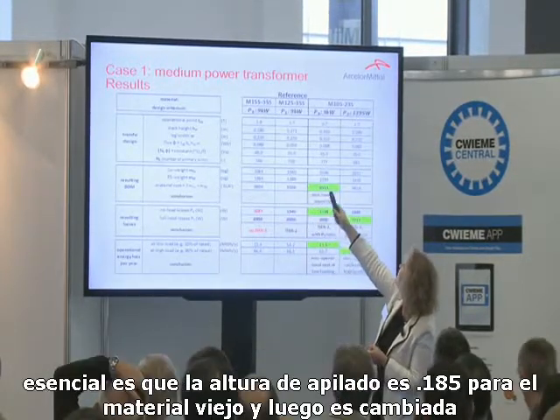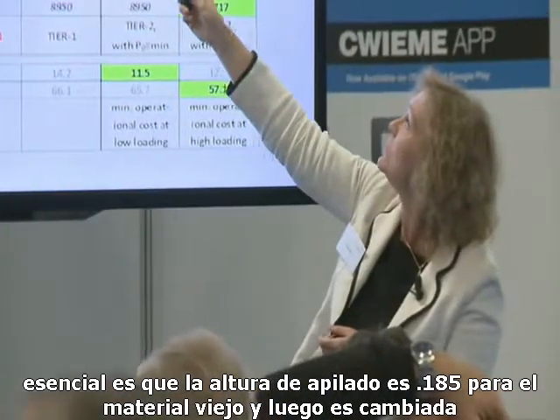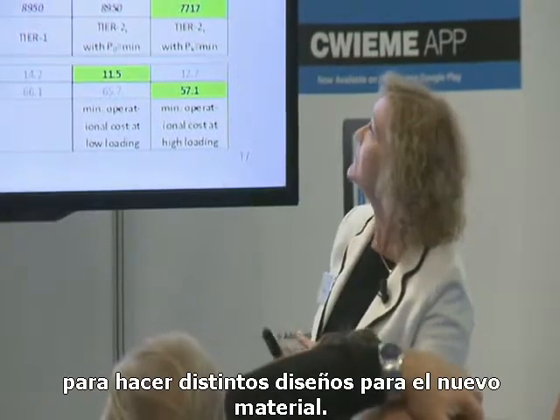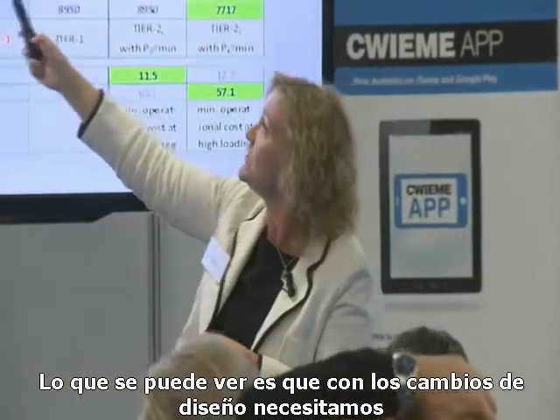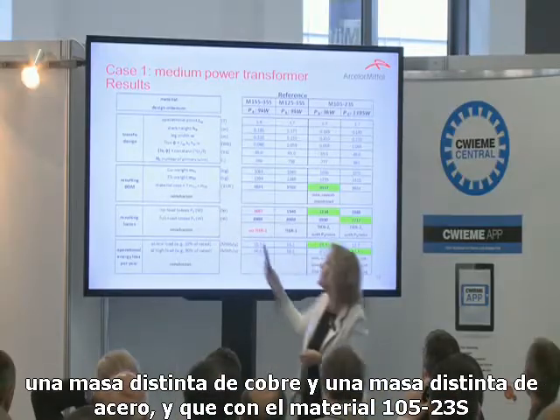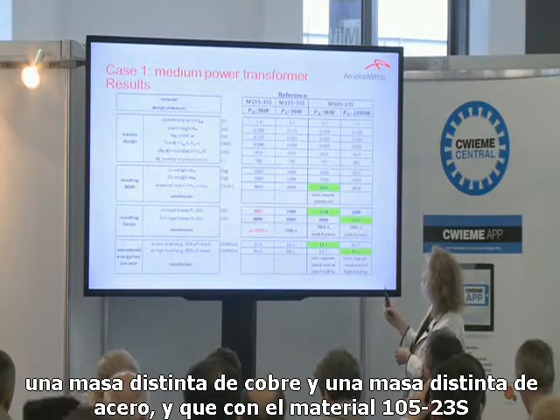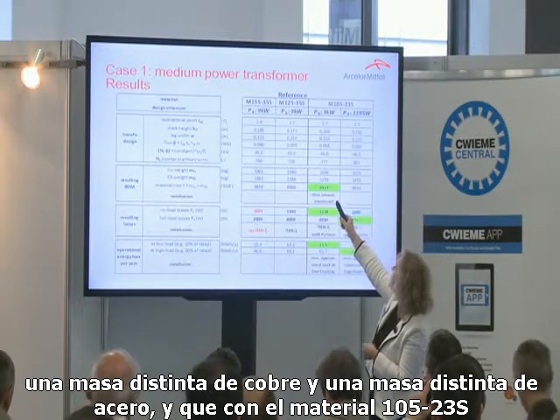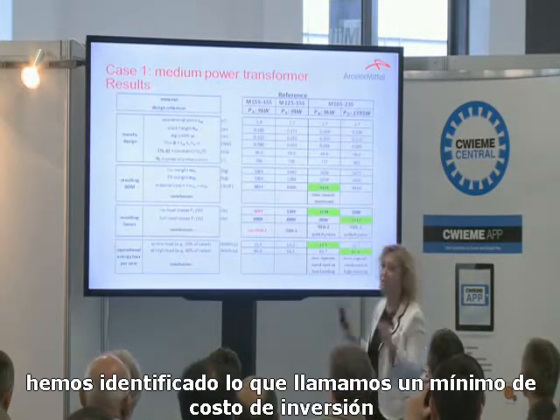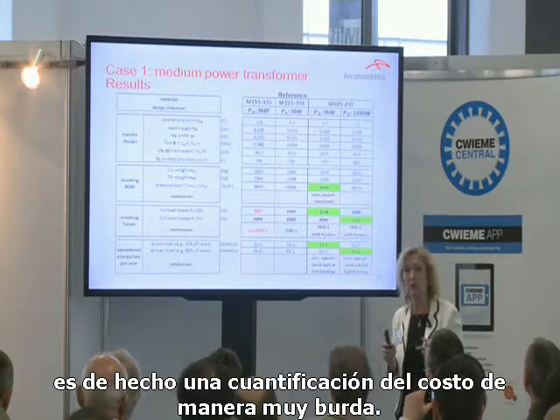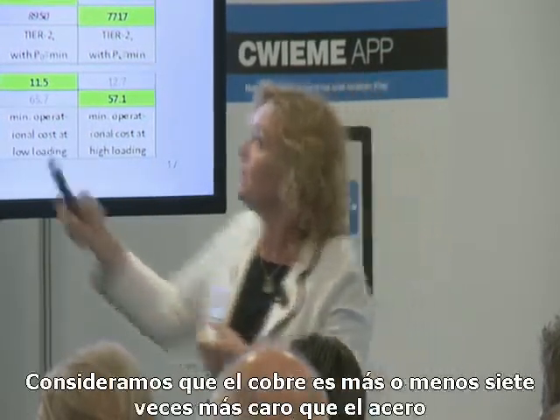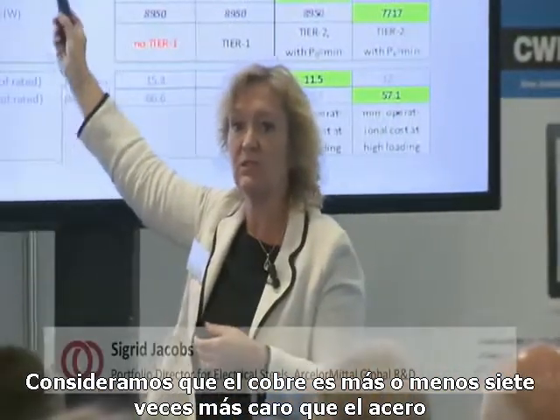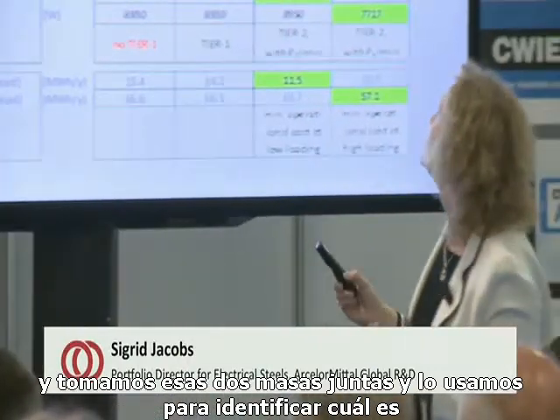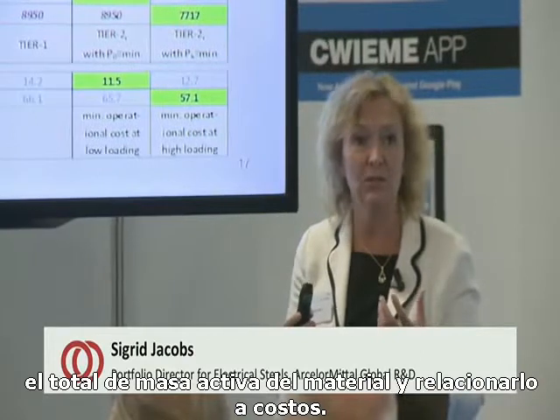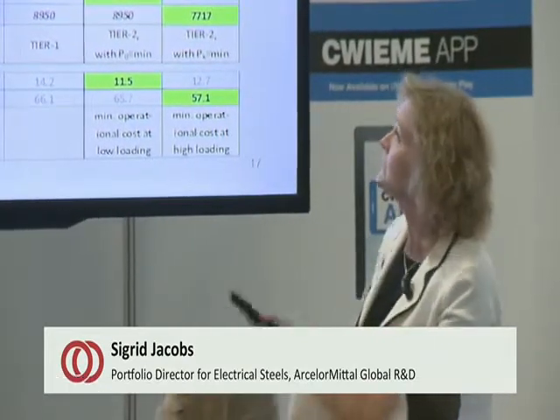and if you look at the geometry, so the transformer design, the essential difference will be the stack height, which is 0.185 for the older material, and is then changed in order to make the different designs for the newer material. What you can see is with the changes of designs, we need a different mass of copper and a different mass of steel, and that with the use of the 10523S material, we have identified what we call a minimum investment cost. It's in fact a quantification of the cost in a very rough way. We consider that copper is about 7 times more expensive than steel, and take those masses then together and use this to identify what the total mass of active material is going to be, and relate it sort of to costs.